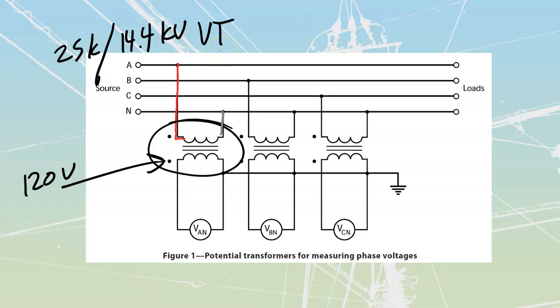What we see over here is a Y to Y type of connection, where on my high side I'm connecting as a Y over to the neutral, and then to my individual lines, A, B, and C. Then on the low side, I see that my low side is going to have a rating of 120 volts. In other words, when this winding receives a full 14.4 kV, this one over here is going to receive a full 120 volts.